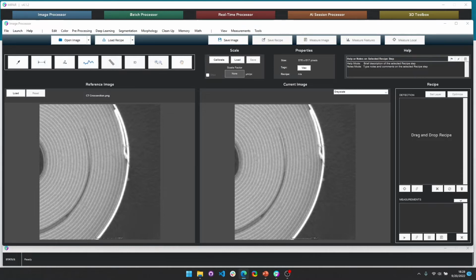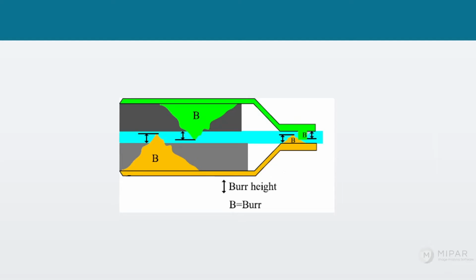So even though you can do electrical testing of the complete component, and it provides a wealth of information about the performance of that component, electrical testing does not provide the failure mechanism in case that component fails, or in case that there is a contaminant in the final build. Very rarely will simply electrical testing highlight that. Let's jump into the presentation here.